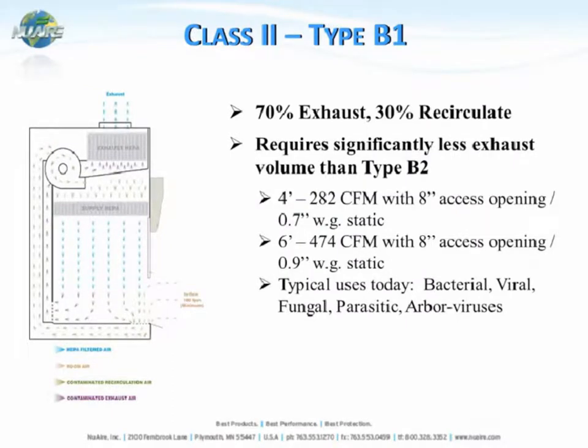From Class II Type B2 cabinets, we move to Class II Type B1 cabinets. This is kind of the inverse of what a Class II Type A2 does — 70% of the air is exhausted, and 30% is recirculated within the cabinet. The benefit of a B1 cabinet involves how it performs in the back half of the work zone, as shown in the illustration. That airflow is not recirculated in the back half, so it functions very much like a B2, where it's one air change and out.